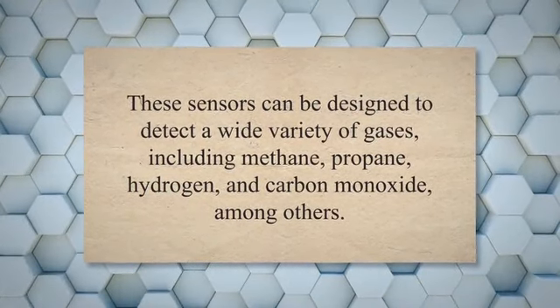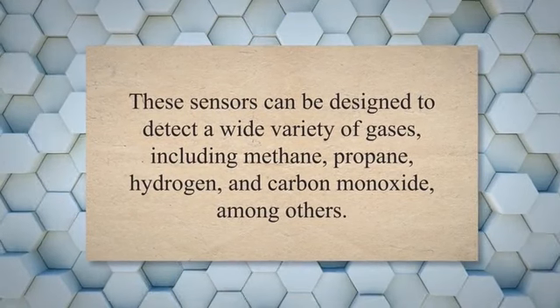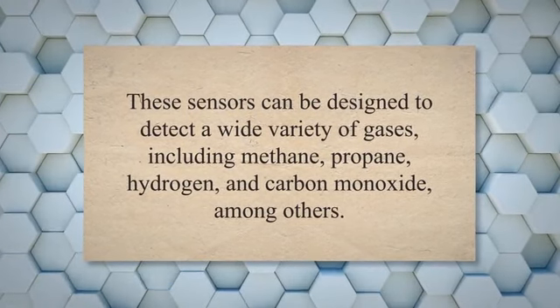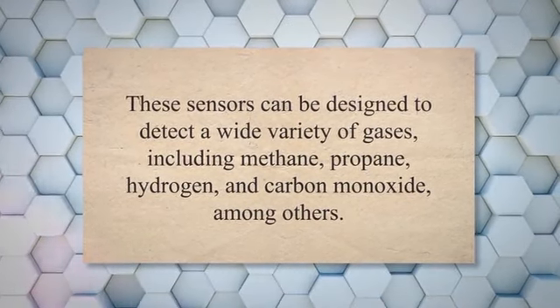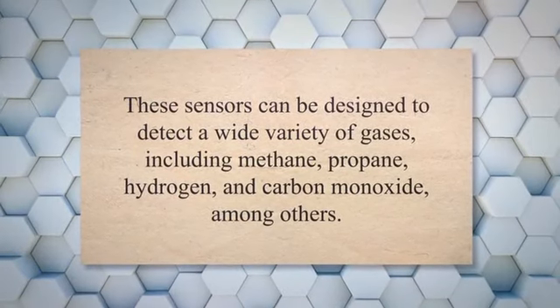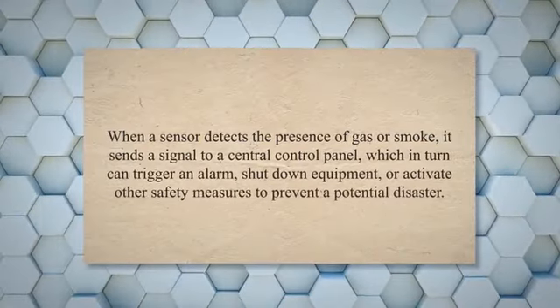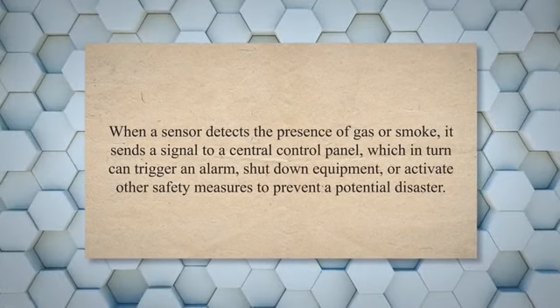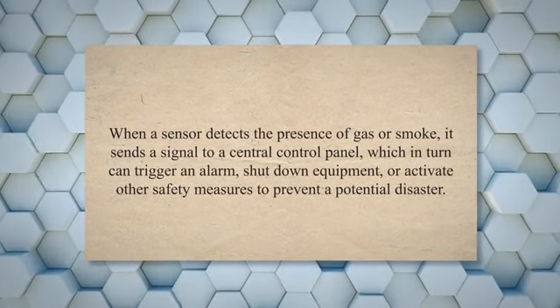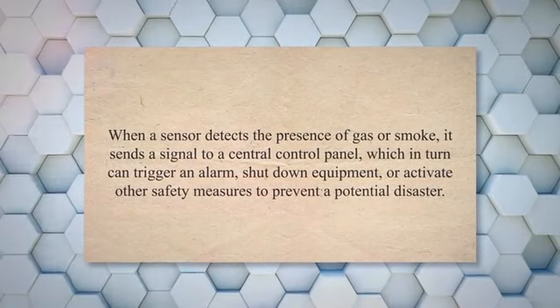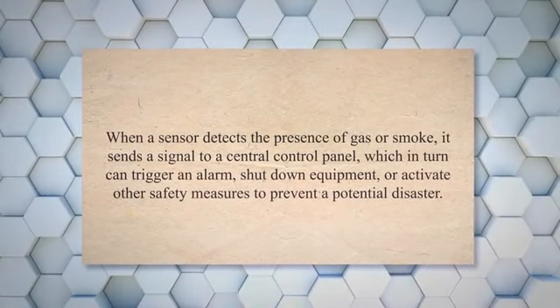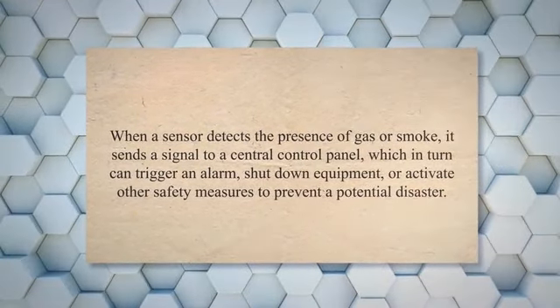These sensors can be designed to detect a wide variety of gases, including methane, propane, hydrogen, and carbon monoxide, among others. When a sensor detects the presence of gas or smoke, it sends a signal to a central control panel, which in turn can trigger an alarm, shut down equipment, or activate other safety measures to prevent a potential disaster.